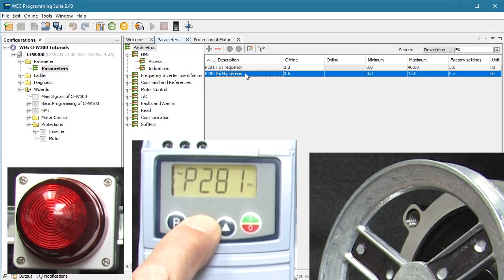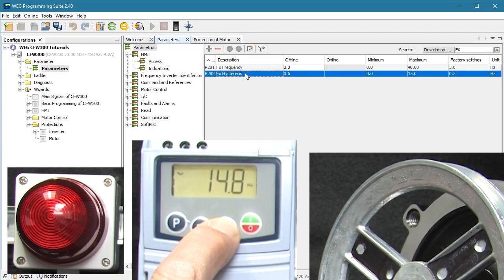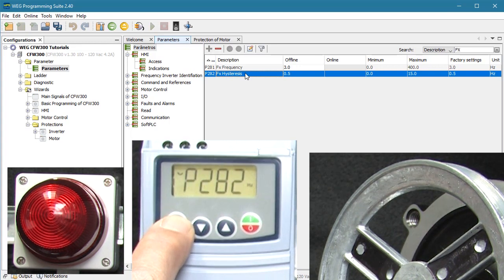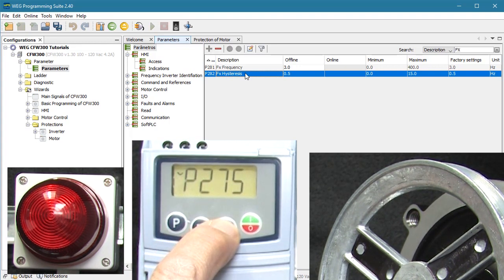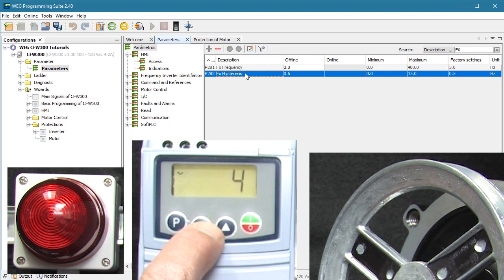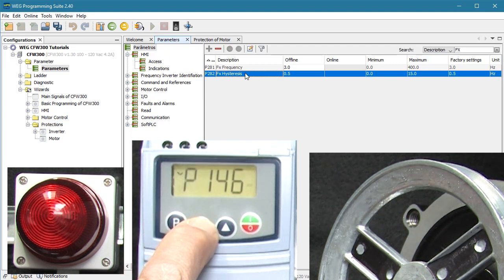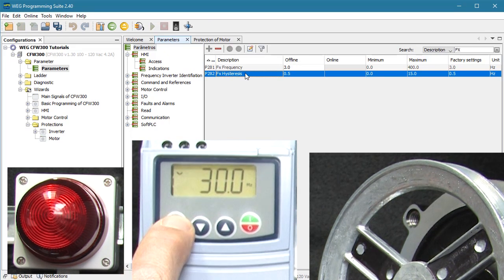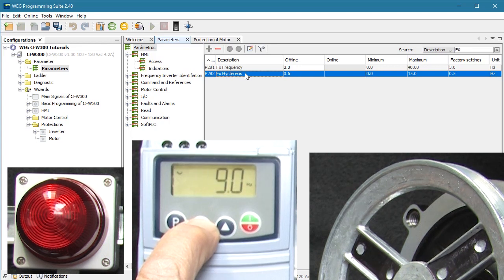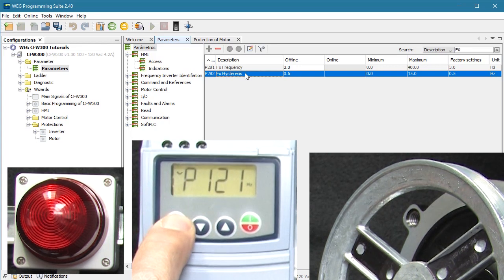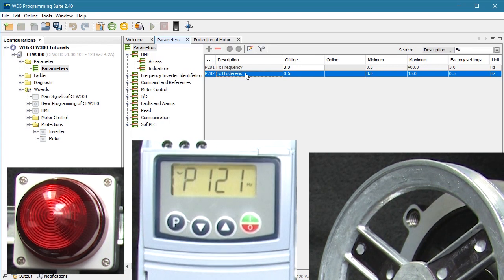Let's go to parameter 281 and set the frequency we want to exceed at 15 Hz. We'll leave the hysteresis at half a Hz. Go back to parameter 275 and tell the digital relay output to go active when the output frequency is greater than or equal to the 15 Hz we just set. Let's go back to parameter 121 and set our keypad reference frequency to start at 3 Hz. So we expect to see the light turn on when we hit 15.5 Hz and turn off when it falls below 14.5 Hz.